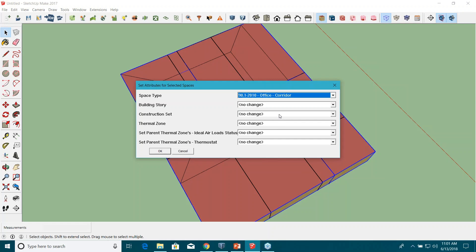When you select 'Corridor' as the space type, it assigns all those internal gain properties and schedules based on DOE reference buildings and ASHRAE 90.1 2010 compliance. The schedules brought into the interface are per DOE reference buildings — it's a good starting point, and you can update them later in the OpenStudio interface. We'll update those schedules and other things in the next video in about two weeks.